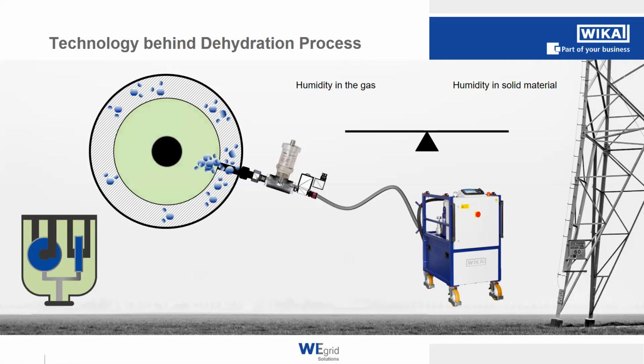And when that has happened, we again start the process, sucking a new portion of gas out, drying it, and putting it back into our compartment. And this process we do again and again, always waiting for a certain amount of time to equalize the humidity from the compartment wall into the gas. With this method, we are not only drying the gas inside the compartment, but also the compartment itself.